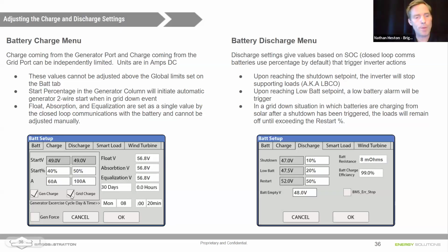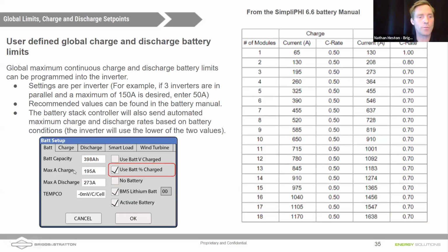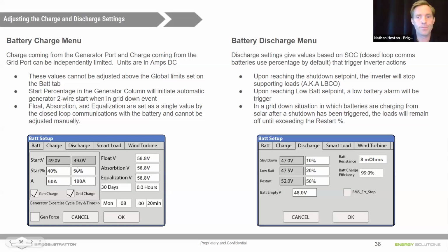You can also check this box for charging if you have something connected to the grid. So if you have a system where the utility is connected to the grid port, 100 amps could be pulled from the utility during a charge cycle. That's the maximum value it'll pull from utility. If you have both solar and grid charging at the same time, it would default to this maximum global charge limit that we mentioned earlier.